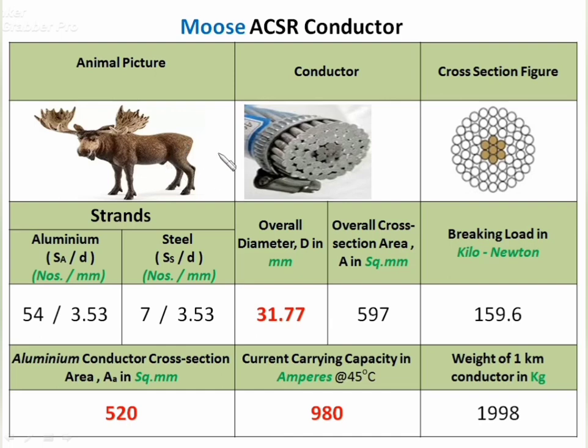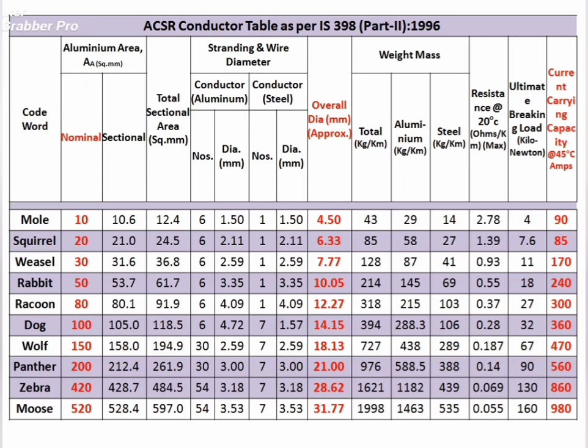Moose ACSR is a type of deer conductor. It has 54 aluminium strands, 520 mm² area, 980 A current capacity, and weight of approximately 2000 kg per km. This is the IS:398 ACSR table — you can see the row of Dog conductor along with other information such as stranding, wire diameter, weight, mass, resistance, and strength. Important columns are highlighted; you can pause and see each row.